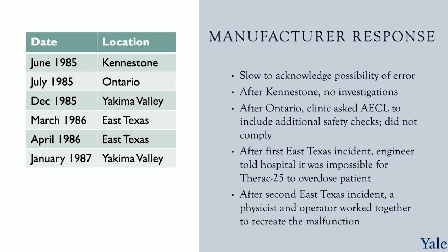The second East Texas incident involved the exact same operator. As before, she used the edit up key to quickly change the mode from x-ray to electron. Again, the malfunction 54 error popped up, and the operator heard the patient moaning for help in the treatment room. The patient described the feeling of fire on the side of his face where he was receiving treatment. After this incident, a physicist at the hospital began his own investigation. He worked with the operator and retraced all of her steps. Through lots of experimentation and button pressing, they discovered that a quick data entry edit from x-ray to electron mode could recreate this malfunction sequence and overdose. Without the effort of these two individuals, it may have taken much more time and many more incidents for the Therac 25 bug to be found.